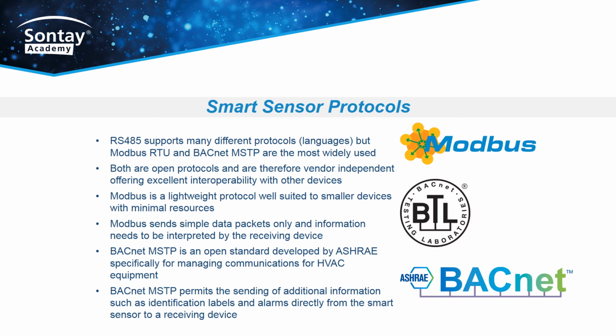BACnet was developed by ASHRAE, the American Society for Heating, Refrigeration and Air Conditioning Engineers, and the first standard was published in 1995. It was specifically designed for building automation applications and has strict rules regarding language constructs, minimum requirements and transmission media. BACnet MSTP, master-slave token passing, uses twisted pair RS485 as its transmission medium and is commonly found in smart sensors, actuators and many field devices.